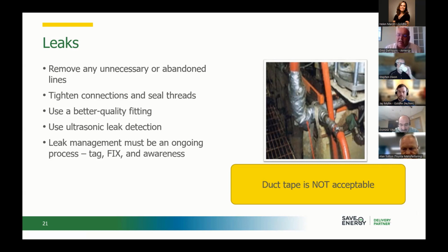We've done a couple of different things, and I agree with you. I've gone into plants where the leak tags are still there from a year ago, six months ago. What I found is you work the leak detection with one of the mechanics, and as you find the leaks, you fix the ones you can get to right then and there, and document it. The ones you can't, you generate proper work orders to the maintenance department. But what I'm finding is leaks are on top of the priority list, but as things go along, other more important items come onto the maintenance schedule, and leaks just get forgotten.